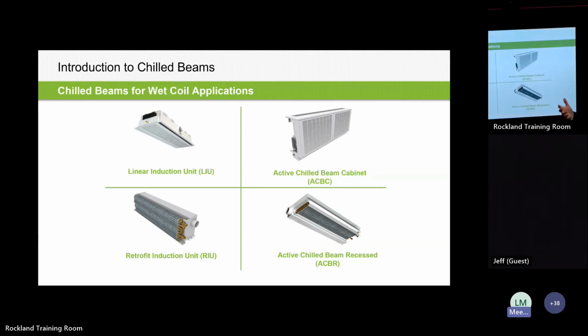And then I know this is going kind of back on what I was just saying about sensible only, but there's also, in the industry, induction units, but updated to have the chill beam type of technology, the new nozzles and design that exist with the chill beams. So you can actually design some of these to have drain pans within them. And I'll show you a video later in the presentation showing the operation of when those start to condense, how does the water fall down into that drain pan? So you can see how that operates.